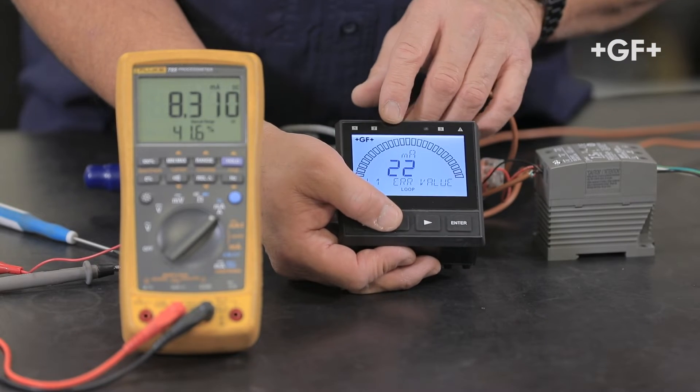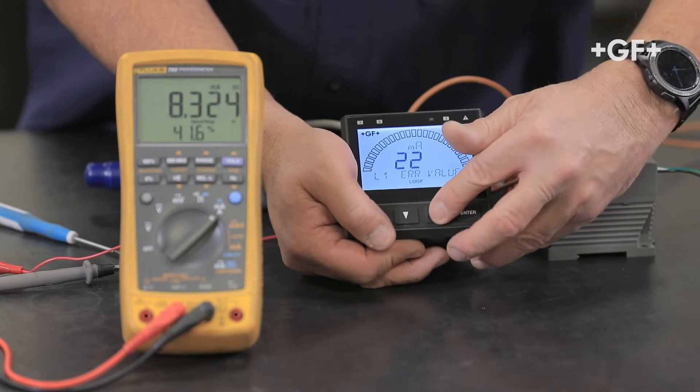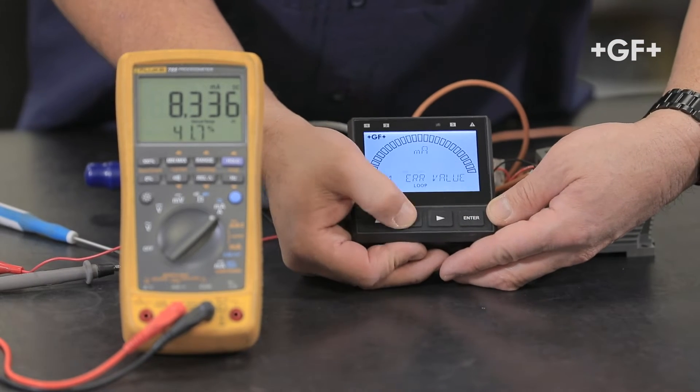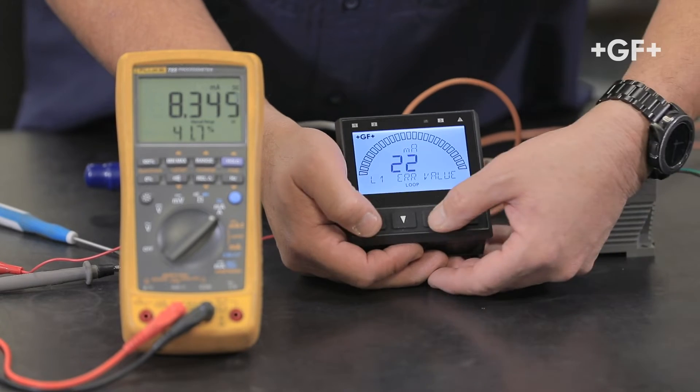This has an error, so I can have the error either set to 22 milliamps or 3.6. Okay, so we'll leave it at 22.